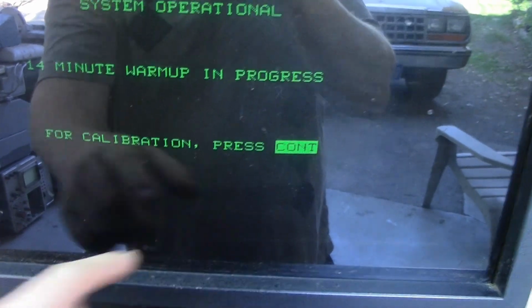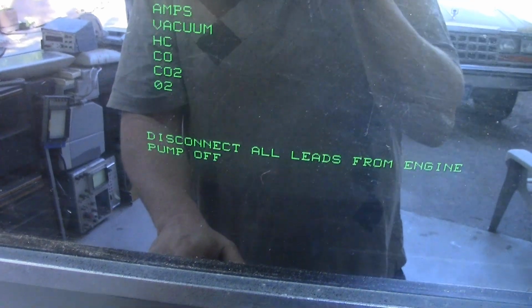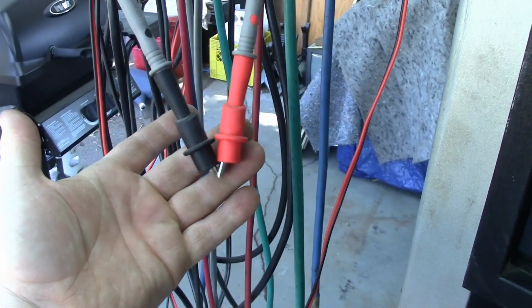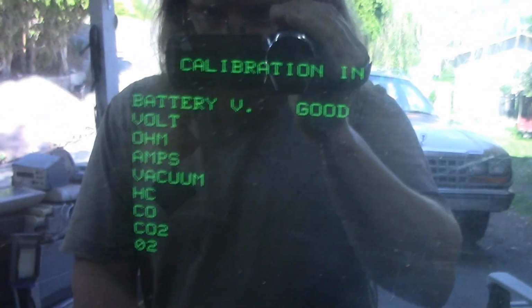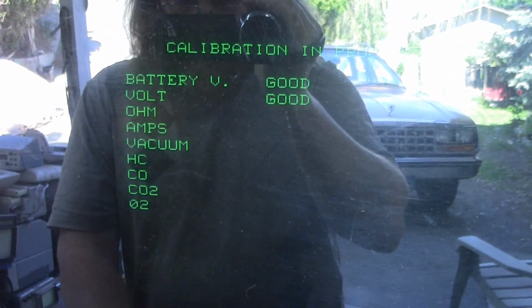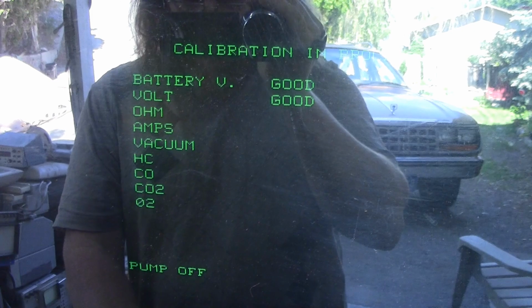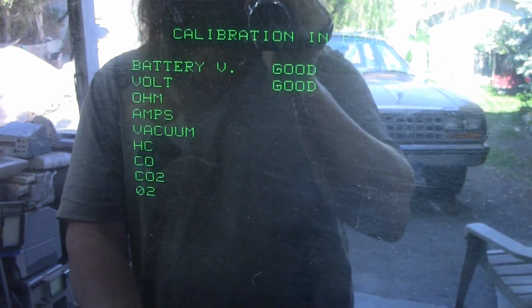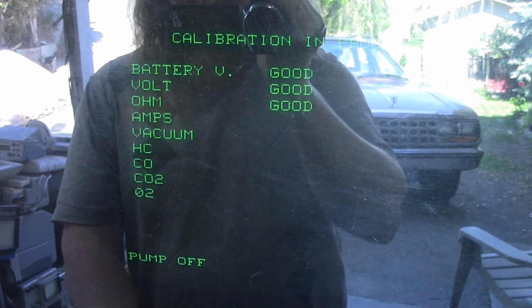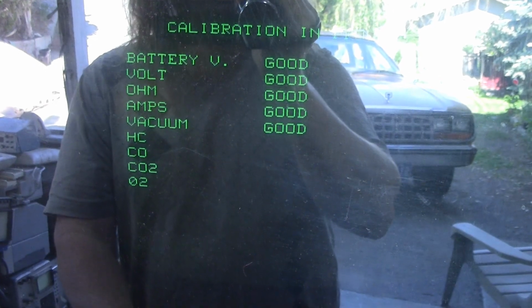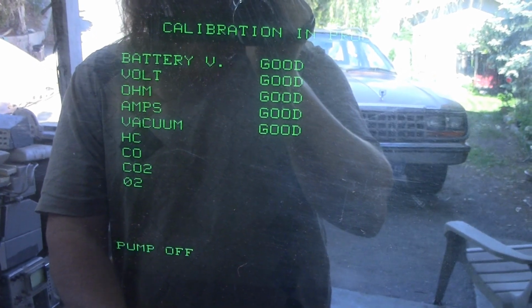So for calibration, press continue, because we still have to calibrate the rest of the harnesses. So I'll do that. It'll tell me to disconnect all the leads from the engine, and I've done that. For the volt ohms, it wants you to bridge the terminals, so I just have those clipped together. And it'll go through those and verify that they're, well, either zeroed out or it sees continuity across it with the volt ohm. And this will take a moment here. So there's the ohm, so it saw that was good. Amps and vacuum, saw that was good.